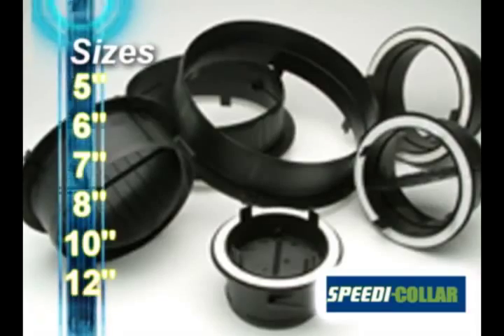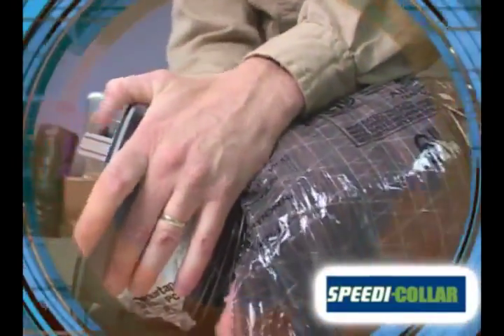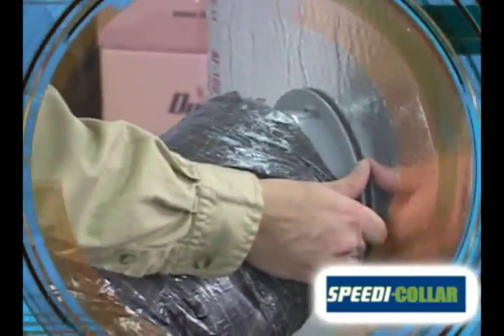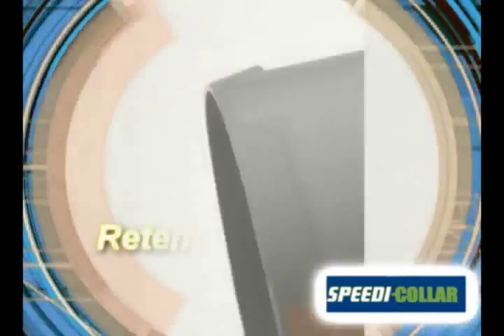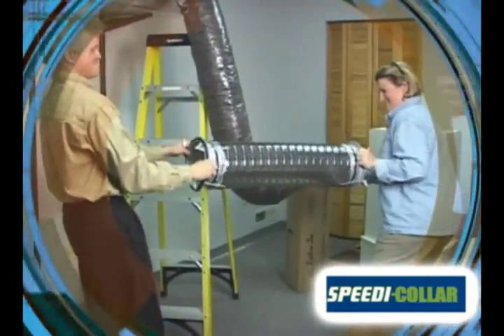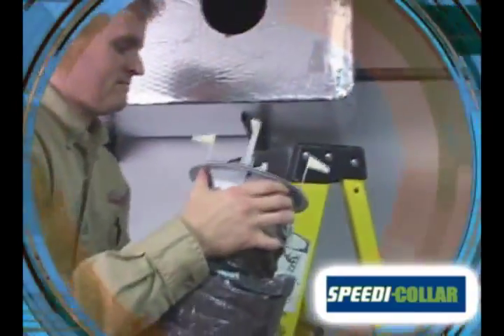Speedi-Collar is made in the U.S. of high-density, UV-resistant black plastic. Speedi-Collar's unique design allows you to save even more time in the field by pre-attaching your flex. Pull the flex inner liner over Speedi-Collar's positive grip retention ring. Use tape, mastic, or a strap to secure the inner lining, resulting in a strong, tight connection.